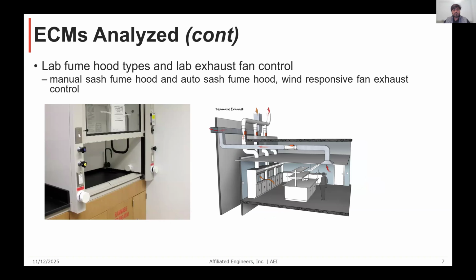As I mentioned, there were several wet labs in this project. So in the last category of ECMs, I evaluated different types of lab fume hoods, for example, manual sash fume hoods and auto sash fume hoods, and also wind responsive fan exhaust control. I'll give a brief overview of these ECMs. Fume hoods are ventilated enclosures that are used to protect the lab occupants from hazardous chemicals. In manual sash fume hoods, the user needs to open and close the sash manually by hand. As a result, there could be significant energy waste, because if the user forgets to close the sash, it could be left open.